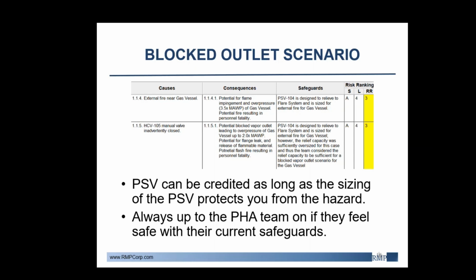It is good that you can credit the PSV in this instance, but this is not always the case. In a liquid overfill scenario, we may pressure up well above MAWP, but that scenario may react differently than an external fire scenario, and therefore the PSV may not be credited. It is always best practice to make sure that your PSV is sized for each specific scenario, whether it be a blocked outlet, liquid overfill, or external fire. Calculations should be made for each consequence.